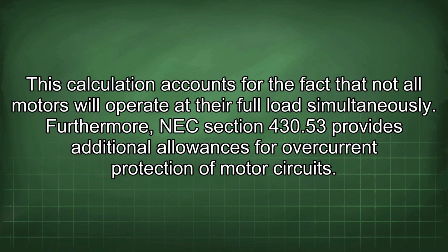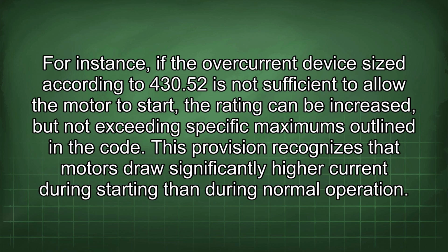Furthermore, NEC Section 430.53 provides additional allowances for overcurrent protection of motor circuits. For instance, if the overcurrent device size according to 430.52 is not sufficient to allow the motor to start, the rating can be increased, but not exceeding specific maximums outlined in the code. This provision recognizes that motors draw significantly higher current during starting than during normal operation.